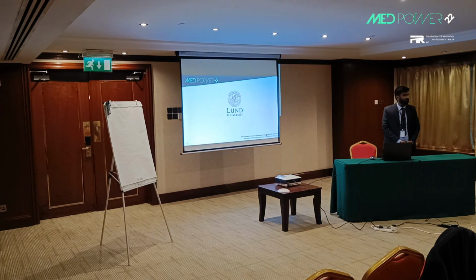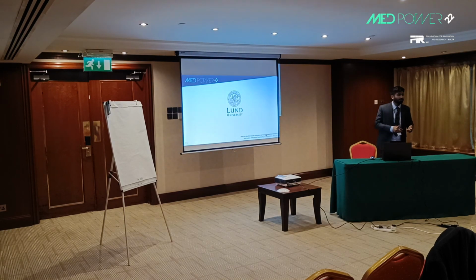Any other questions? Yes, I have a question. When you say the transformer size, you also change the reactance, the impedance of the transformer? Yes. It's the same per unit, but it is actually changing. Okay. And how are you getting second harmonic components? Because of the time it's not shown over here, but in the paper we have shown that with transformer energization, because of the non-linearity, it draws a lot of second harmonic current. Non-linearity where? In the saturation of the transformer core.